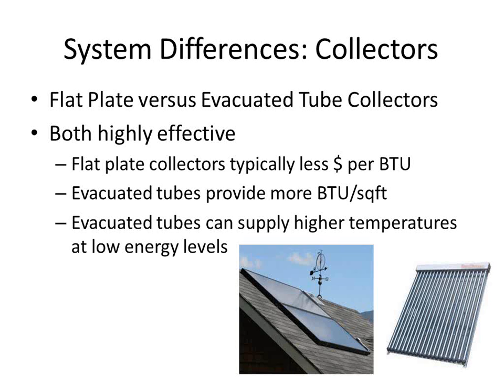With a flat plate collector, even if you put more collectors up to keep the overall energy amount high, the temperature itself is going to drop off. You may get more energy out of it, but the temperature level is going to be less. So if you're trying to generate higher temperatures, for example, if you're trying to work with a baseboard heating system where you want temperatures much higher, evacuated tubes are a more effective technology to use than a flat plate. If you're looking at domestic hot water where you don't want it hotter than 120 degrees at point of use, or radiant floor systems, flat plate collectors are more than adequate. They give you much more than adequate temperature rise to work with those systems. I'm going to have the notes on the two.